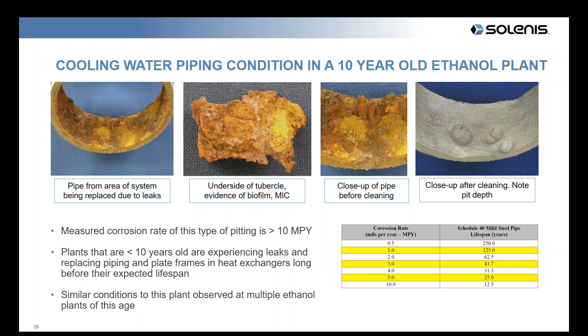The pitting we're seeing is well in excess of 10 mils per year. The little table on the bottom right indicates that if you've got over 10 mils per year of corrosion, your lifespan for that piping is going to be 12.5 years. Most plants would expect their piping to last a lot longer than 10 years—something like 20 to 25 years is not uncommon. We've observed this at a number of plants we've worked with.